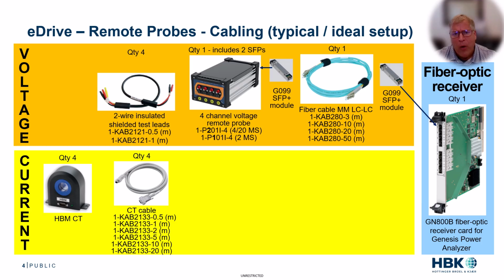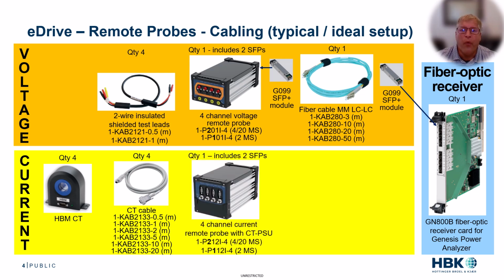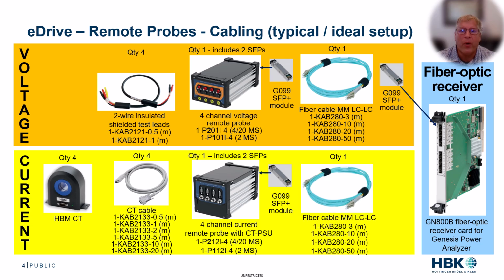Now for current, with an embedded CT power supply remote probe, you can use 4 CT cables, cab 2133, to connect the current from the CT to the 4-channel current remote probe input. Then connect the output of the current remote probe to the mainframe's second port on the GN800B fiber optic receiver card, and you can use a fiber optic cable, cab 280, to do so. Now, you want to be sure and refer to the user manual for further details, such as inserting the SFP plus modules.